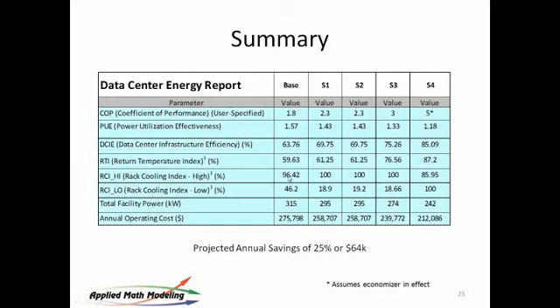RCI started off 96. Even though we had too much air, we were too hot in certain places. We did get it to 100, but as we began to drive temperature up, we suffered a little bit near the tops of some racks. So this is a judgment call, whether you turn your supply temp up so that you have no hotspots, or you manage it with respect to where you put your equipment in the racks. We got the RCI low up out of the single, well, below 20 range and moved it to 100.